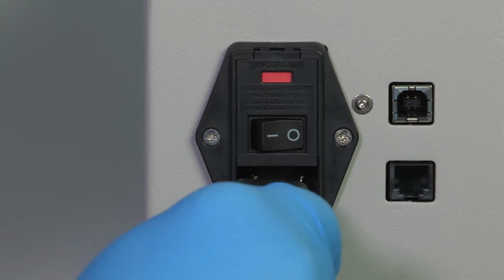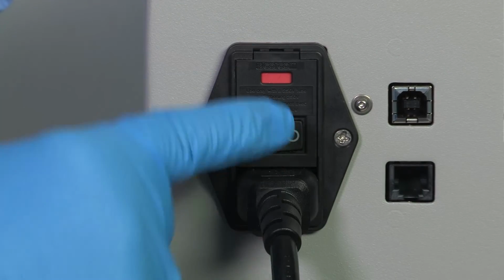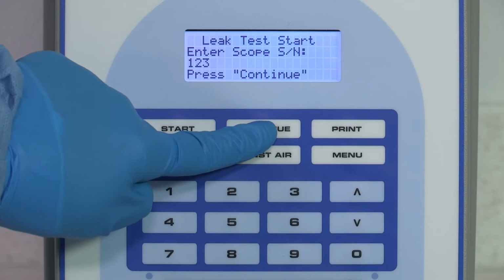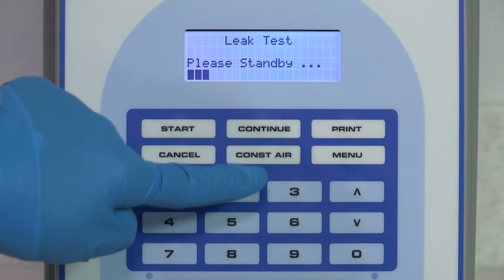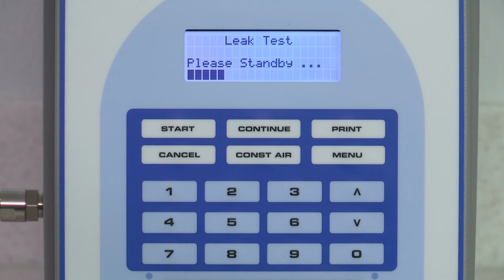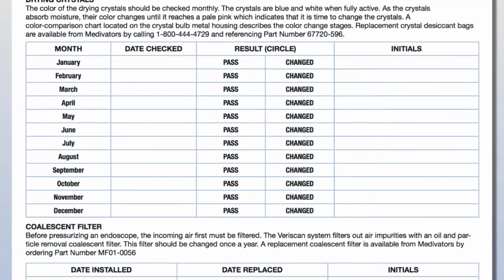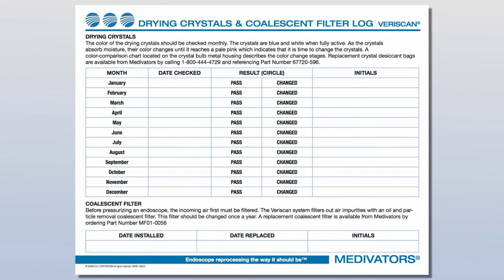Plug in the VERISCAN Leak Tester and turn the system power back on. Always perform a QA test after replacing the drying crystals to confirm proper operation. Record the date checked and the result, passed or changed, using the drying crystals log.